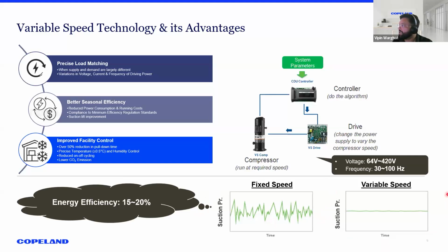While if it is variable speed, it will ensure that the suction pressure is maintained at a constant level, as it is going to modulate with the help of the variable speed drive, and thus the compression efficiency will increase. That's how the precise temperature will be maintained, and thus it will help you maintain the humidity very well. Of course, as variable speed is driving the compressor, the on-off cycles will go down, and thus the overall energy consumption will also come down. It will reduce energy use by 15 to 20%, even 25% to some extent. This will help reduce the scope emissions of your facility.